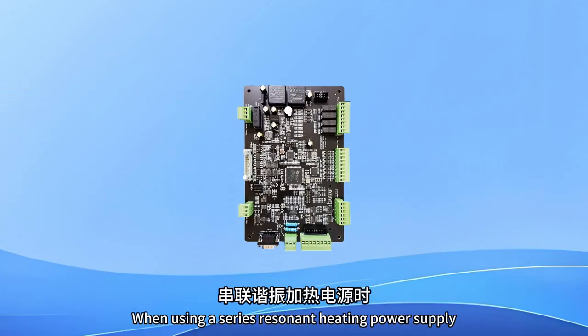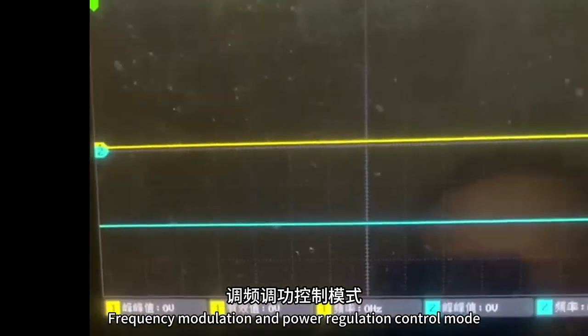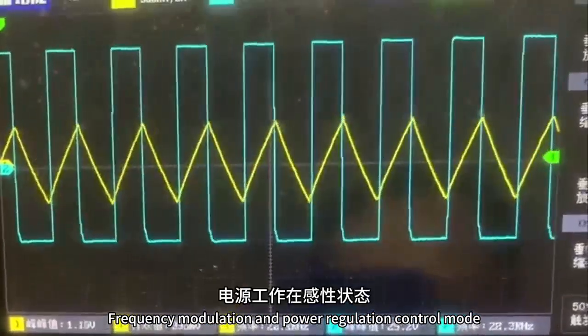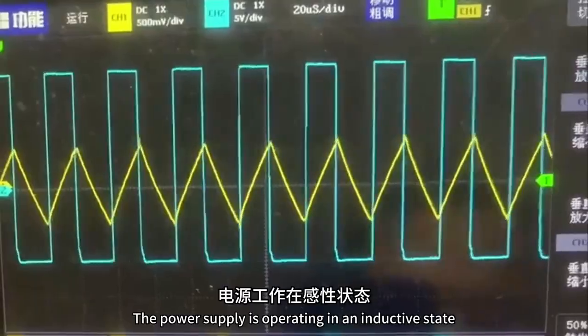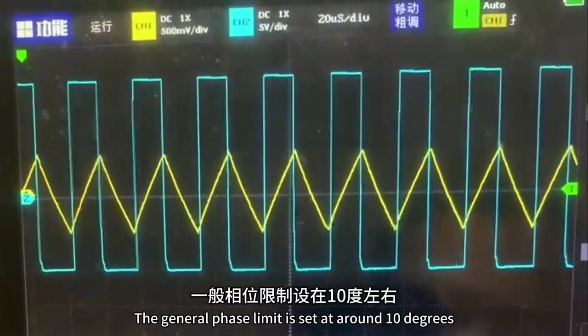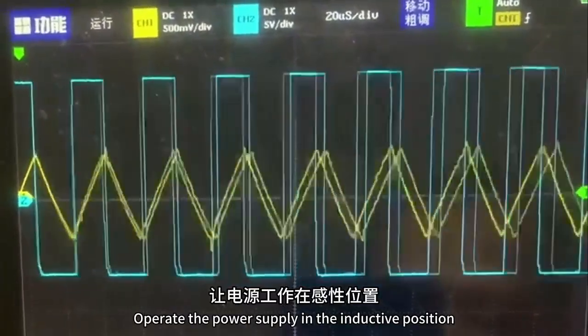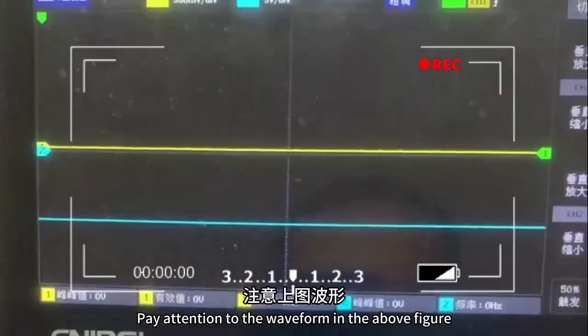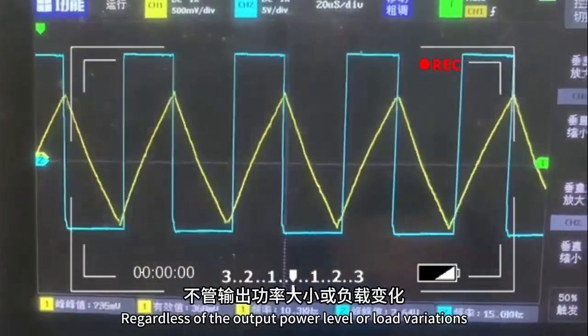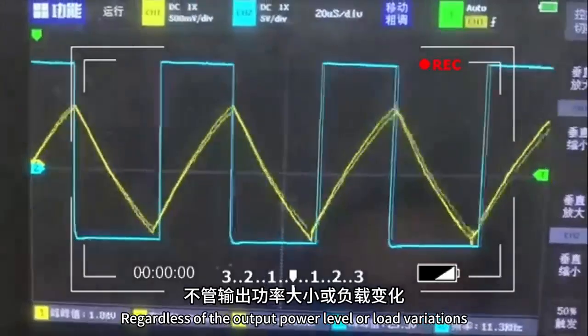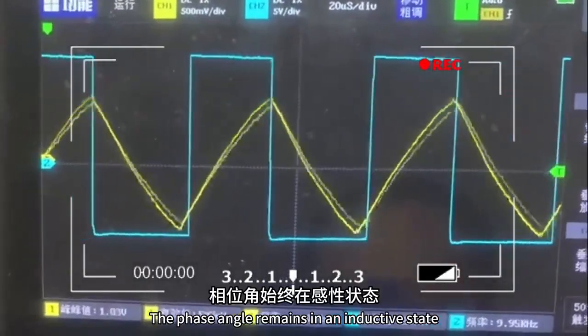When using a series resonant heating power supply with frequency modulation and power regulation control mode, the power supply is operating in an inductive state. The general phase limit is set at around 10 degrees. Operate the power supply in the inductive position. Pay attention to the waveform in the above figure. Regardless of the output power level or load variations, the phase angle remains in an inductive state.